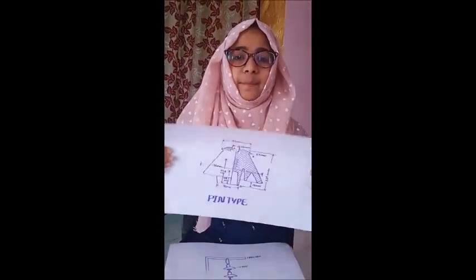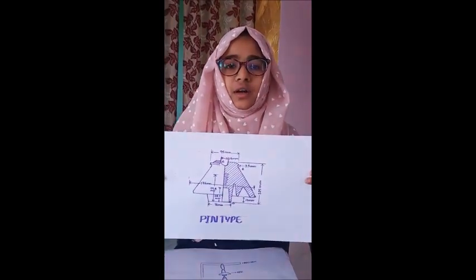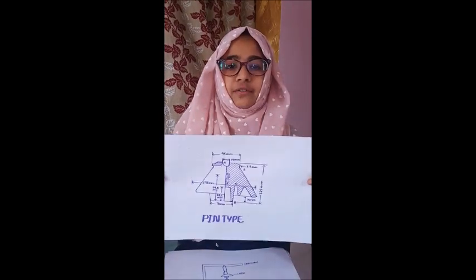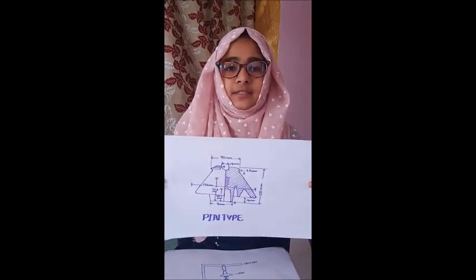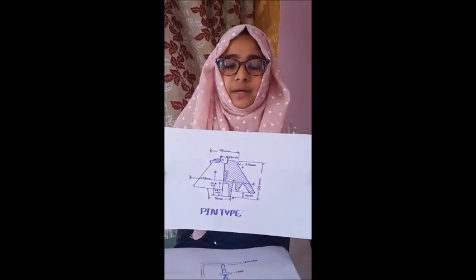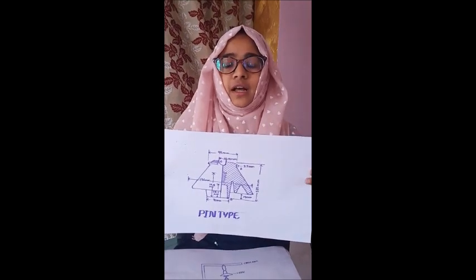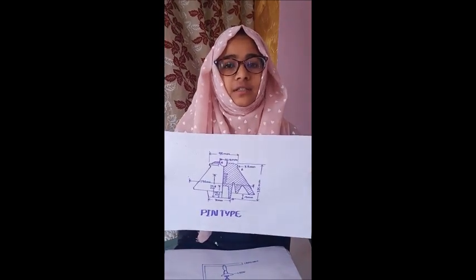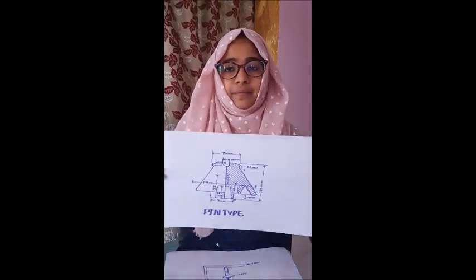There are five types of insulators. First, pin type insulator: used for 11 kV; for higher voltages like 33, 45, 66 kV, two or three pin types are used. There is a groove at the top for the conductor. Pin type insulators are restricted up to 33 kV. Second, suspension type insulator: also called disc insulator, connected one after another in series in a metallic structure. Used for higher voltages and maintenance is easier and cheaper compared to pin type.